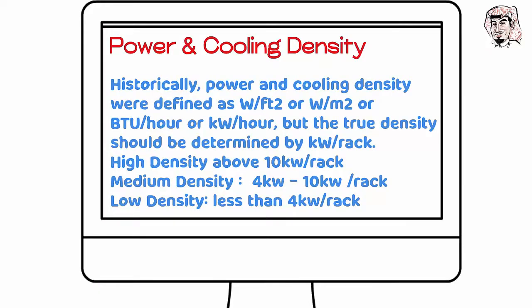Power and cooling density. Historically, power and cooling density were defined as watts per square foot, watts per square meter, BTU per hour, or kilowatts per hour, but the true density should be determined by kilowatts per rack. High-density equipment usually consumes more than 10 kilowatts per rack, whereas medium density is between 4 and 10 kilowatts per rack. And finally, low density is less than 4 kilowatts per rack.